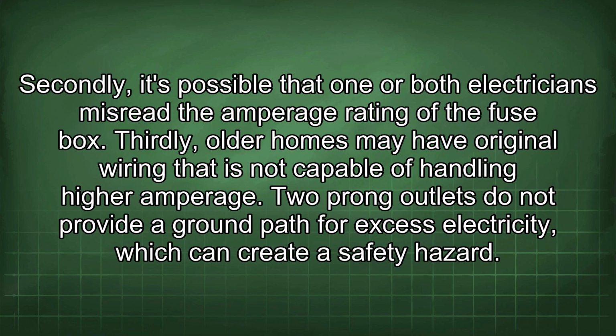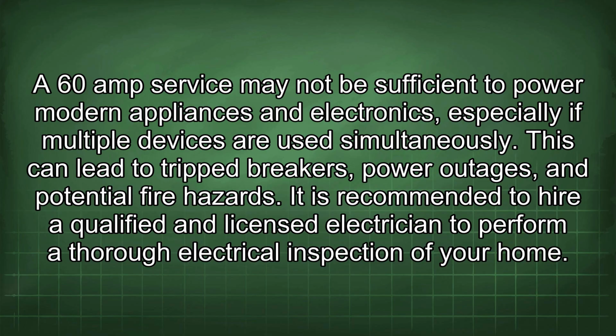Secondly, it's possible that one or both electricians misread the amperage rating of the fuse box. Thirdly, older homes may have original wiring that is not capable of handling higher amperage. Two-prong outlets do not provide a ground path for excess electricity, which can create a safety hazard. A 60 amp service may not be sufficient to power modern appliances and electronics, especially if multiple devices are used simultaneously. This can lead to tripped breakers, power outages, and potential fire hazards.